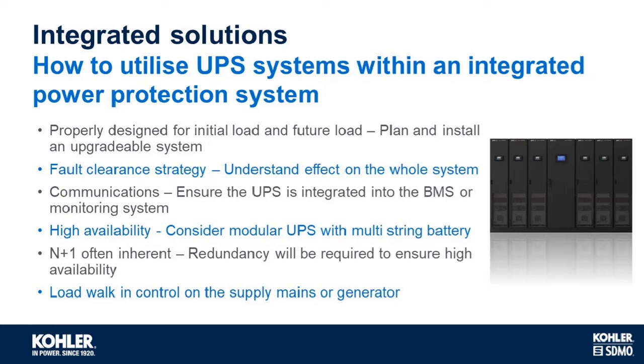So we often consider that a modular UPS with multiple strings of batteries is going to give you high availability. But one of the other things that greatly affects that is the redundancy in the systems. So we would often supply an N plus one type system with the redundancy. This obviously can also be incorporated in the generator systems as well. And the redundancy and the mean time to repair will greatly increase the availability of that UPS system. But it's all about choosing the right systems for your load and your application. And that availability is critical in understanding what you're going to design.